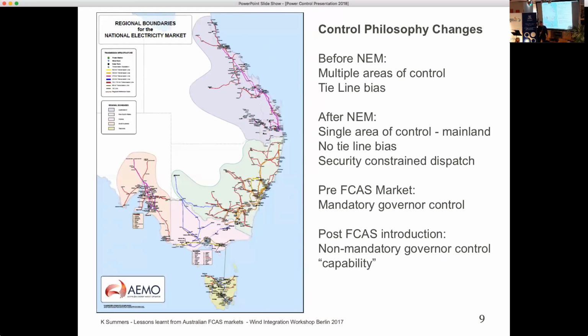Before the market started, we had mandatory governor control with tight deadbands on the governors of the synchronous machines, and that enabled all the synchronous machines to operate within a very close tolerance of their nominal rotational speed of their shafts. What we have done is said that governor control is not mandatory, but you can offer us a service under frequency control to actually provide frequency control.